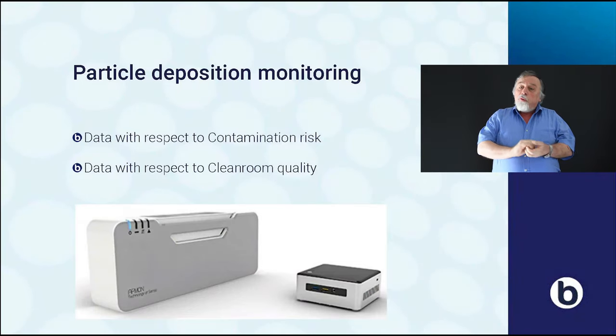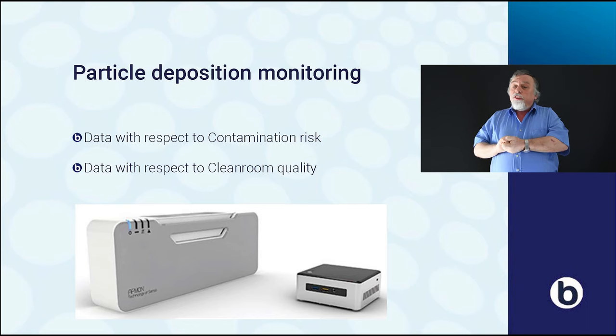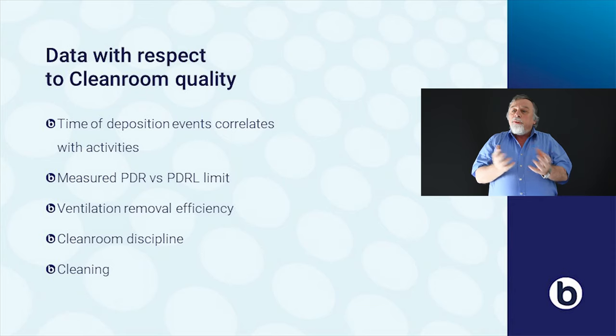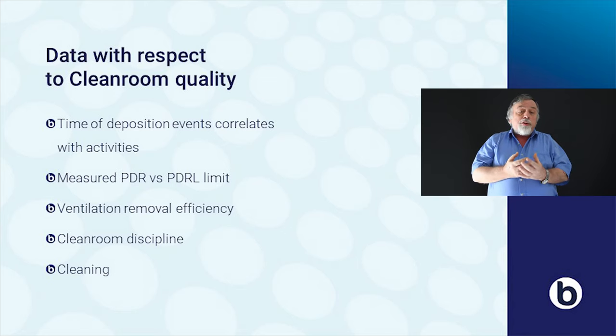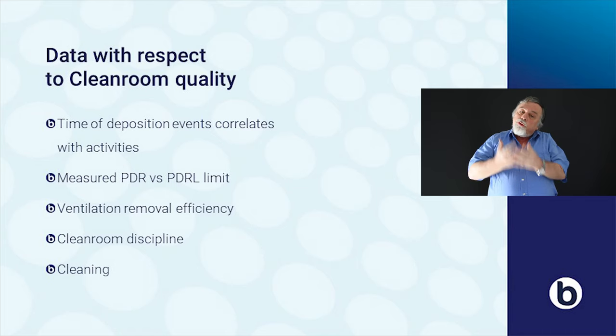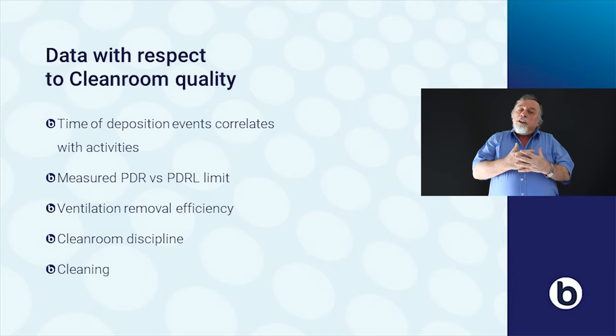Particle deposition monitoring: acquiring particle deposition data gives you information on contamination risk — how much is my product at risk — and also on cleanroom quality: how good is my ventilation, how good is the discipline of people working in the cleanroom, and how good is the cleaning program? The time of deposition correlates with activities. With real-time monitoring, you can see when a high number of particles are depositing and when it's low. You can also compare the actual particle deposition rate to the limit set by your risk assessment.